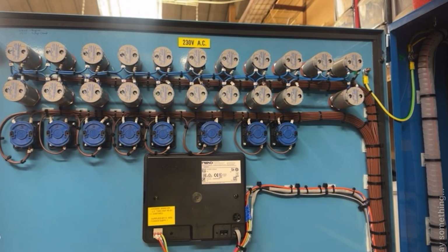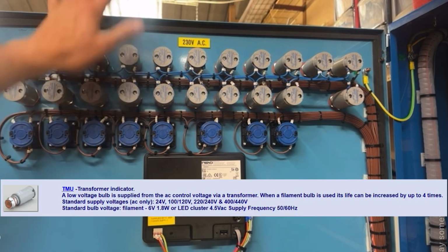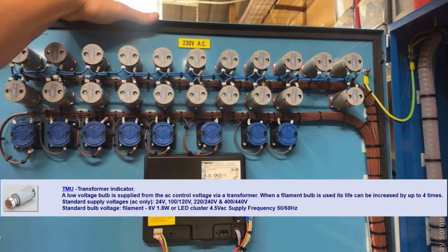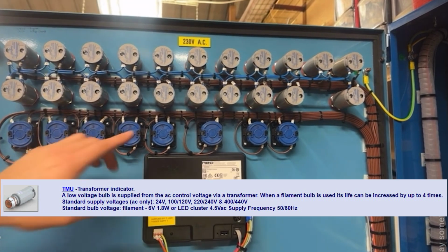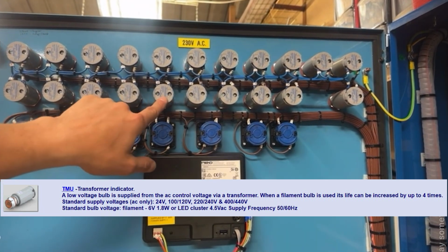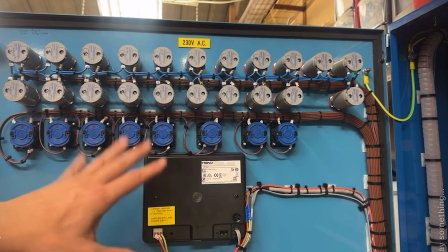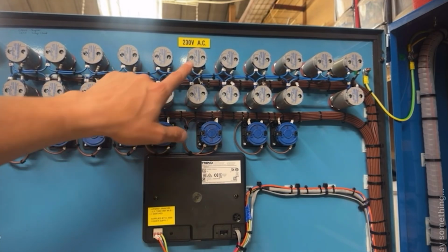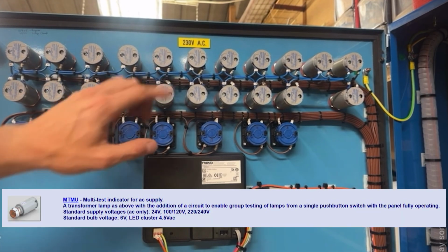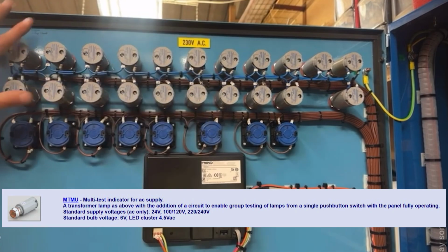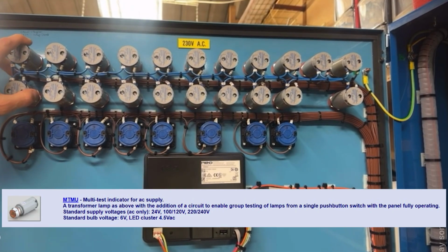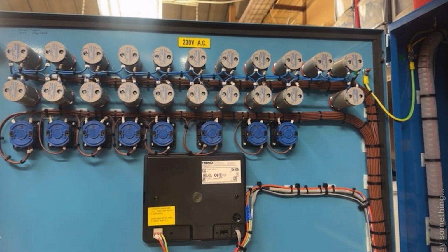The reason they use tranny lamps is because it keeps all the mains inside, but on the outside, accessible, if someone sticks a finger in they'll only get 6 volts. These particular ones are 2-terminal tranny lamps, which means they don't have a test function. On a test tranny lamp, on the front of the panel you'd have a test button that would energise all the lights for testing purposes so you could check all the lamps worked. These particular ones do not have that.